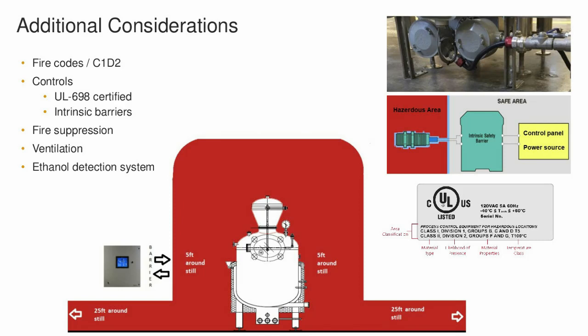There's actually ways to vent your space in an engineered fashion that would even eliminate the C1D2 classification. And that has to be done by an engineer to look at the space, look at the airflow, the makeup air, et cetera. So that's one way to do it, is to have an engineered solution on your vapors. And it still doesn't preclude doing the C1D2 on your electronics. So that's what I'm going to talk about a little bit here.